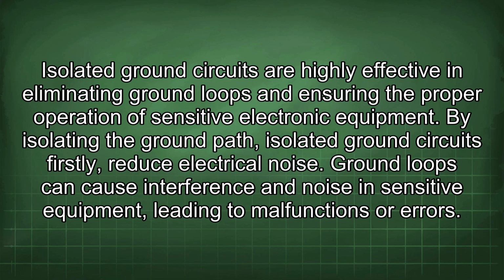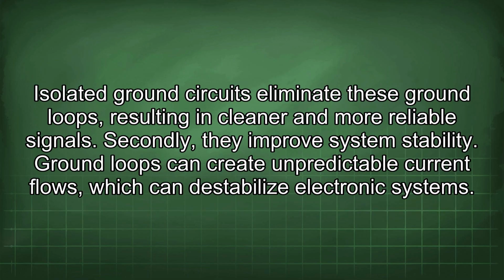By isolating the ground path, isolated ground circuits firstly reduce electrical noise. Ground loops can cause interference and noise in sensitive equipment, leading to malfunctions or errors. Isolated ground circuits eliminate these ground loops, resulting in cleaner and more reliable signals.